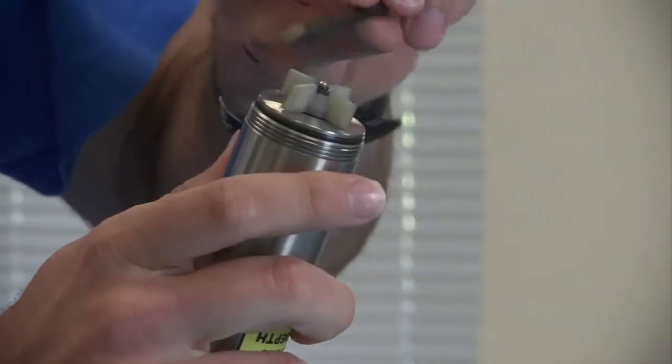When this is in the water, should you have no thrust washer underneath the impeller, then when the impeller makes contact with the housing it can cause excessive friction and cause the shaft to break off.